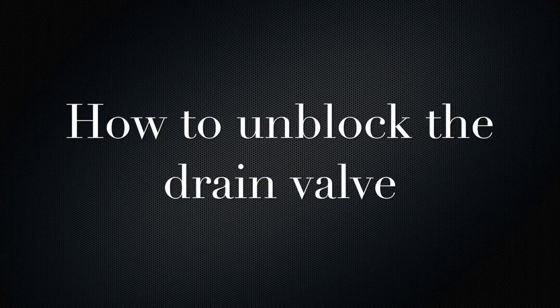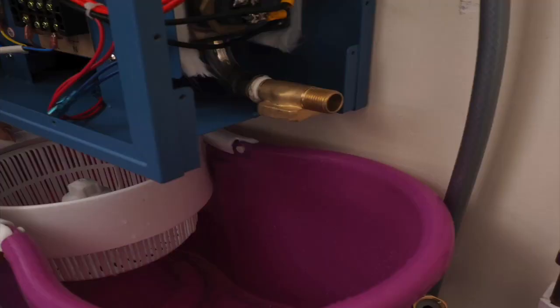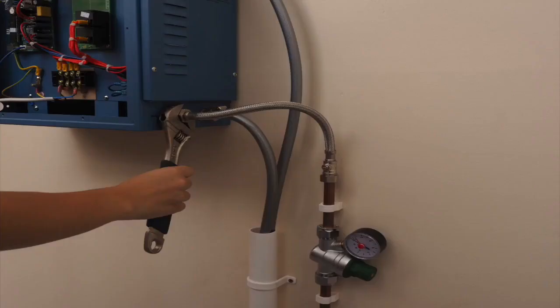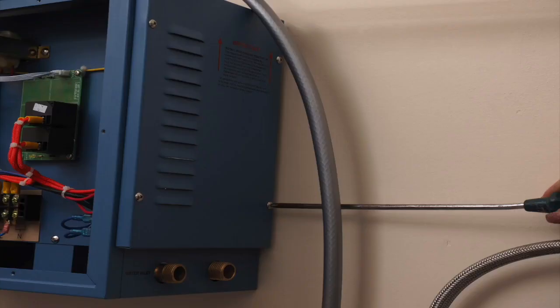We strongly advise the machine is removed, and this is done on a workbench with no electricity plugs or sockets around. If you choose to do this while the generator is in place, you must isolate all power to anything in the same area. Make sure you have a bucket ready underneath the steam generator. It may be useful to have another person helping to hold the bucket. Remove the water and drain connections.